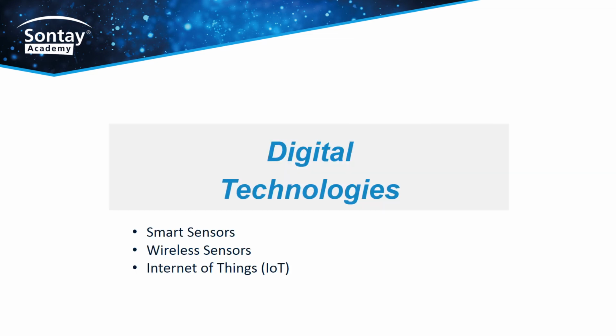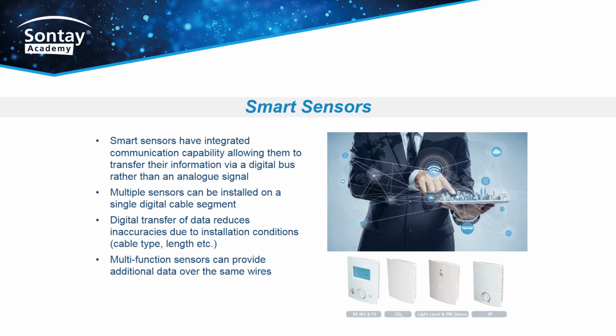Now let's look at digital technologies. They include smart sensors, wireless sensors, and Internet of Things. Smart sensors. Smart sensors have integrated communication capability, allowing them to transfer their information via a digital bus rather than an analog signal. Multiple sensors can be installed on a single digital cable segment. Digital transfer of data reduces inaccuracies due to installation conditions, such as cable type and length, etc. Multifunction sensors can provide additional data over the same wires.